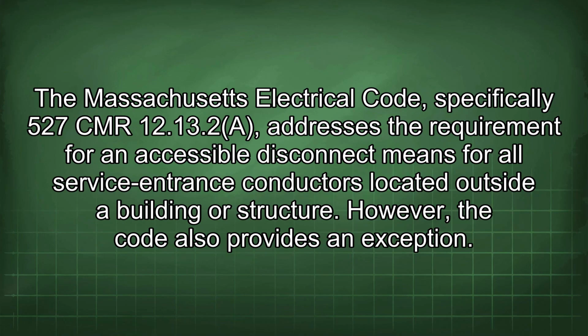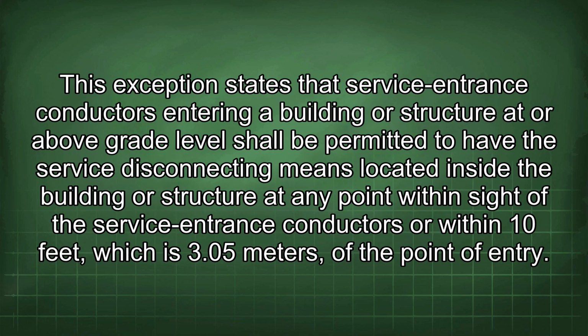The Massachusetts Electrical Code, specifically 527 CMR 12.13 2A, addresses the requirement for an accessible disconnect means for all service entrance conductors located outside a building or structure. However, the code also provides an exception. This exception states that service entrance conductors entering a building or structure at or above grade level shall be permitted to have the service disconnecting means located inside the building or structure at any point within sight of the service entrance conductors or within 10 feet, which is 3.05 meters, of the point of entry.